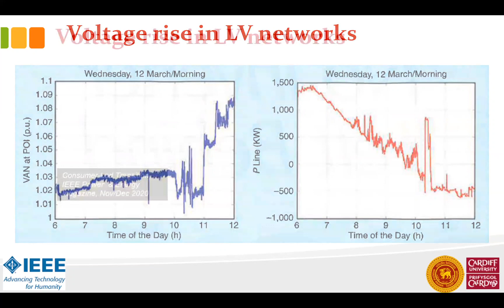So this is a problem. In Europe, if that voltage goes above 1.1 per unit, that is statutorily, or legally, not allowed. The same thing was experienced in South Australia. You can see that there were so many sites above the upper limit, creating voltage rises.